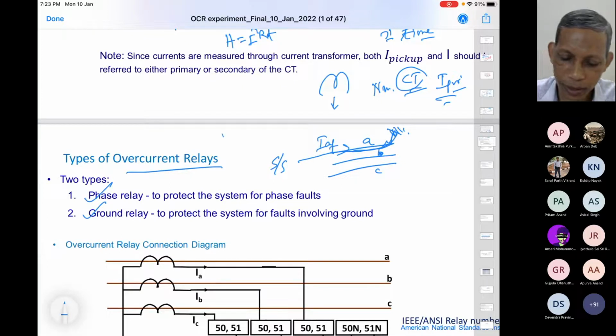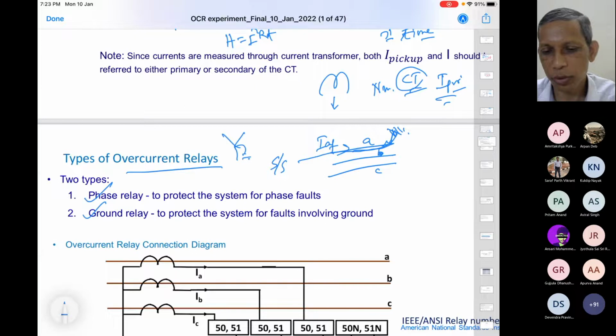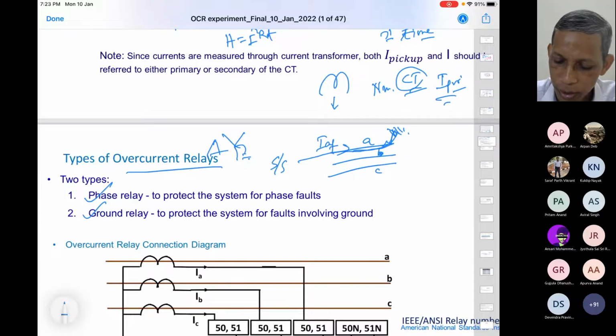Typically you consider this the star ground on the low voltage side and delta on the high voltage side, in an 11 kV to 415 volt supply system. Therefore, this is considered a grounded system. In this path, you see that phase A has a large current, not the other two phases. Now think about another situation.